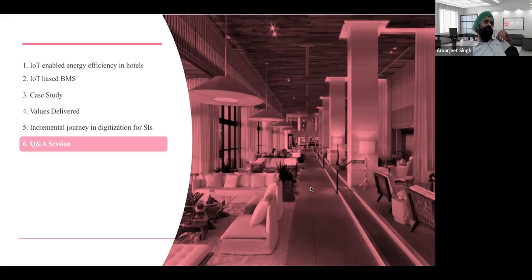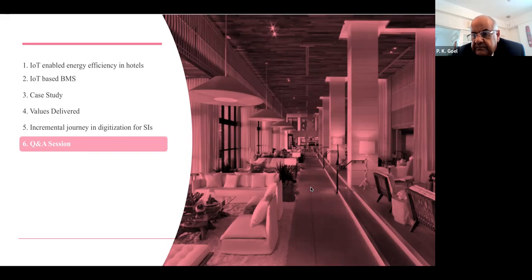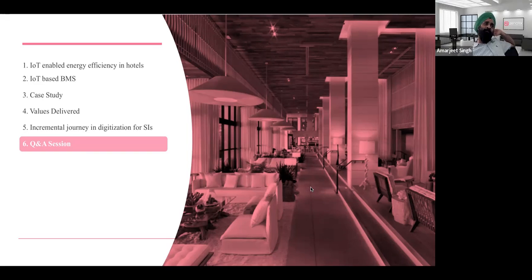I think that's a very good point. Often when a building is designed, the HVAC system is designed for the worst case scenario - a fully occupied building, June weather, especially in Delhi, 45-48 degrees outside, fully occupied, and that's how you provision the HVAC. Now often most buildings, most of the time, are operating not in the worst case scenario but something lower.